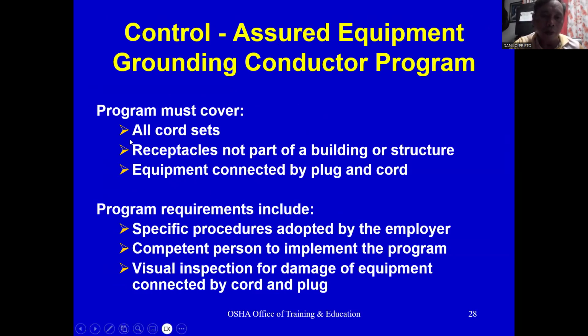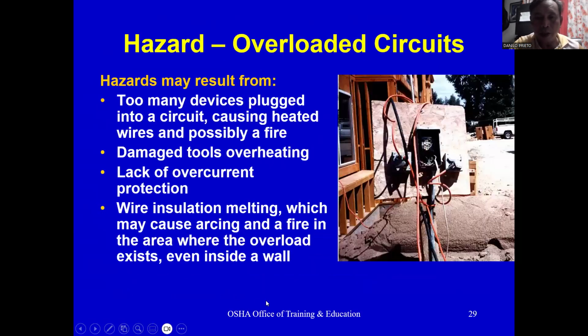Control: assured equipment grounding conductor program. The program must cover all cords, receptacles not part of a building or structure, and equipment connected by a plug and cord. Program requirements include specific procedures adopted by the employer, a competent person to implement the program, and visual inspection for damage of equipment connected by a cord and plug.